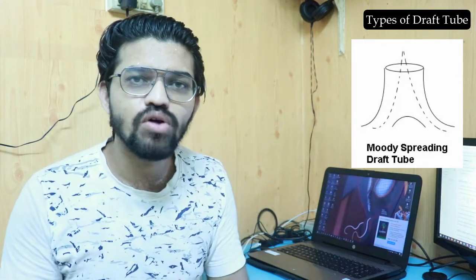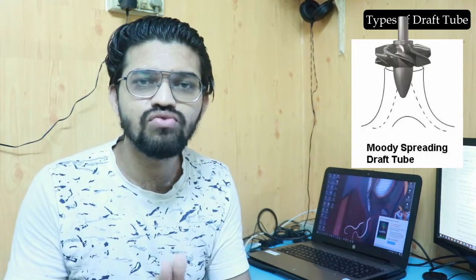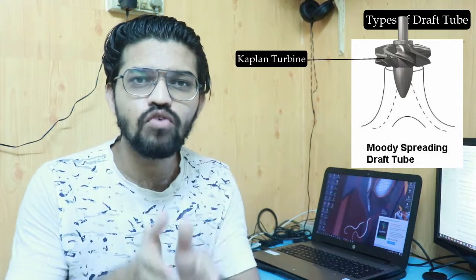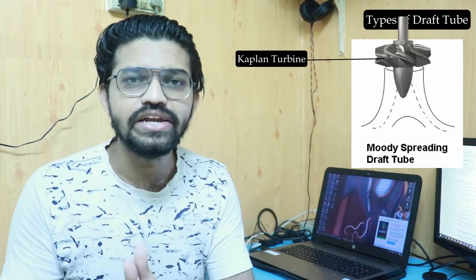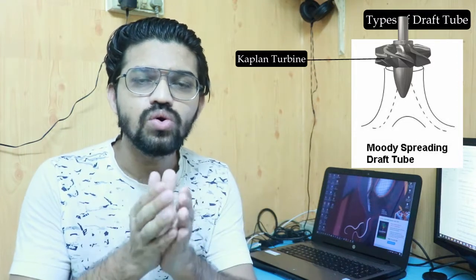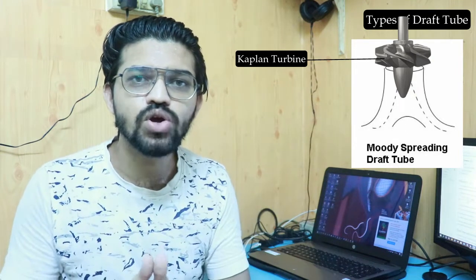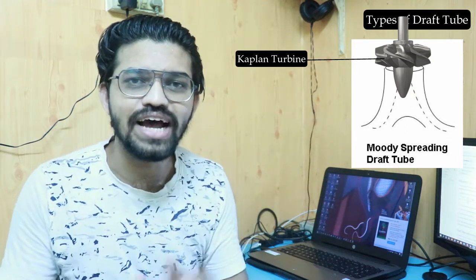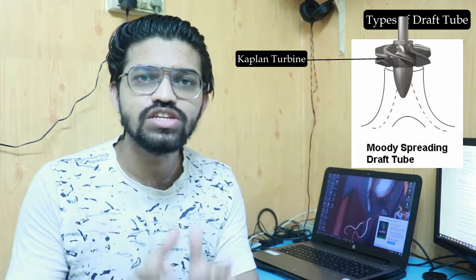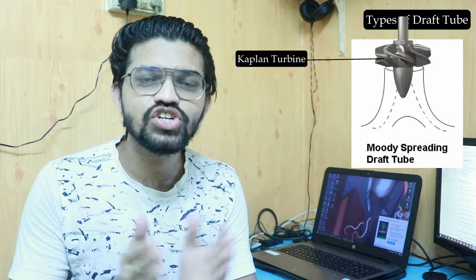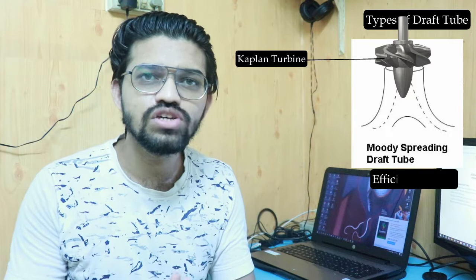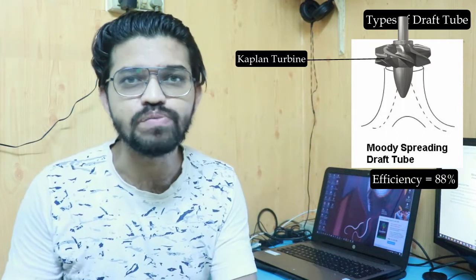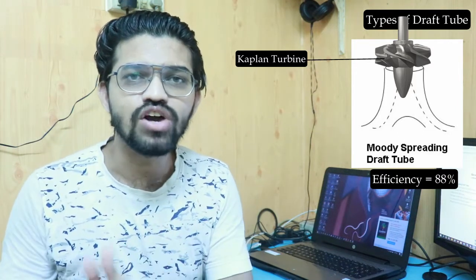The last type is the moody spreading tube, also known as the hydrocone. This type is especially suitable for the Kaplan turbine, which has maximum kinetic energies at exit. This draft tube splits the flow into two different parts — it has one inlet and two outlets — to divide the kinetic energy. The efficiency of this type is around 88%, and it is used in vertical shaft turbines.